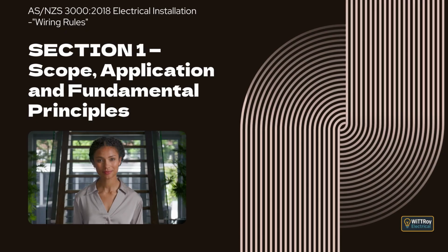Method 3. Obstacles. Obstacles prevent accidental contact with live parts. They are not designed to stop deliberate actions, but they help prevent an accidental bump or touch. Method 4. Placing out of reach. Live parts are positioned far enough away that a person cannot reach them from a normally occupied position. Remember, RCDs are not recognized as a sole means of basic protection. They can support these methods, but they cannot replace them.